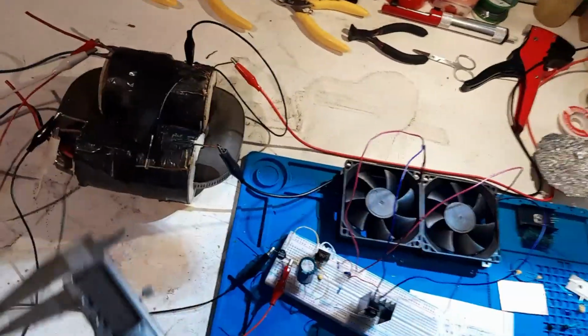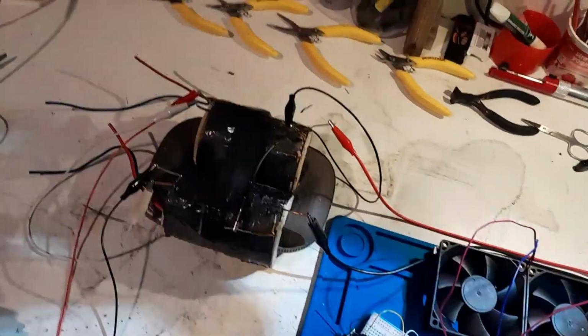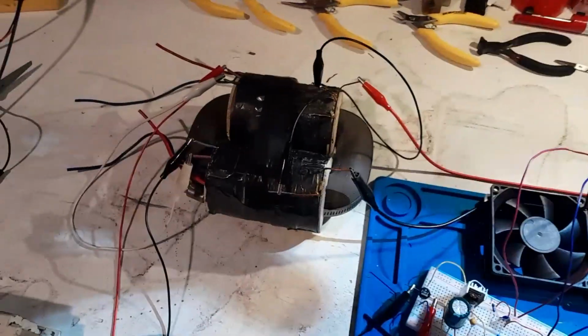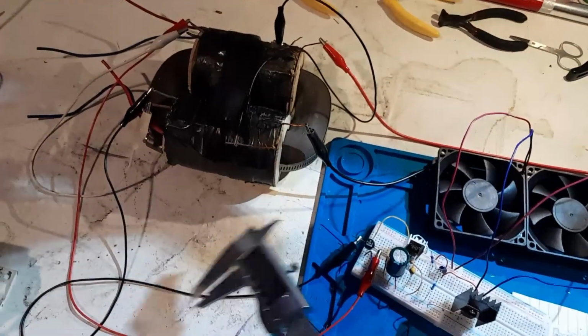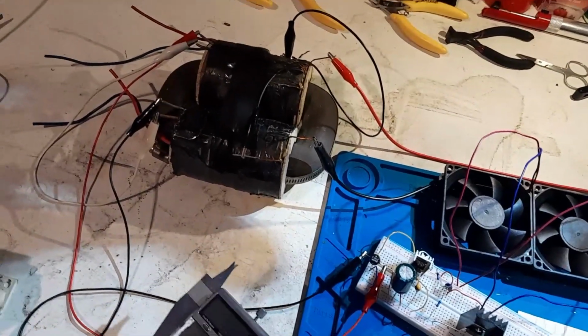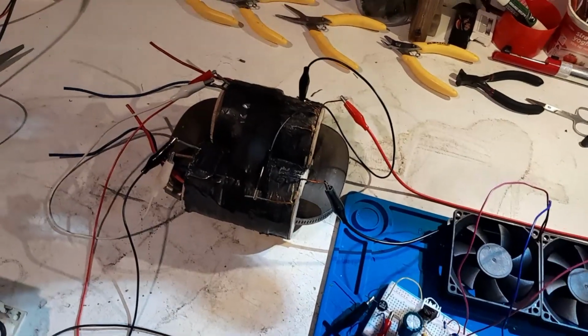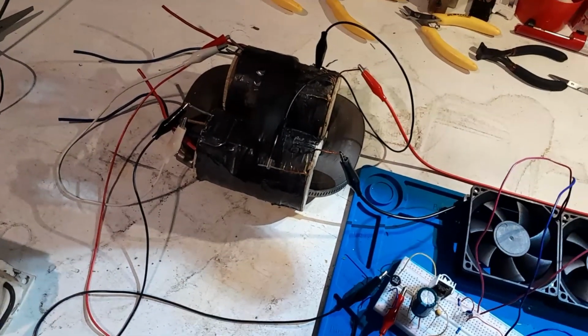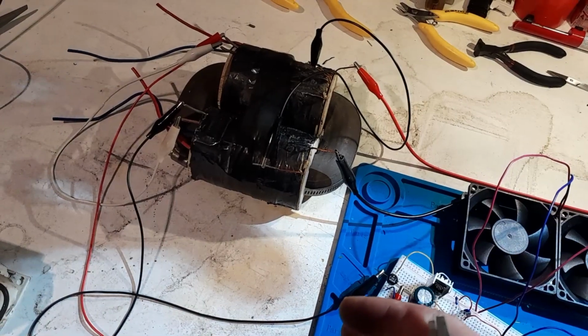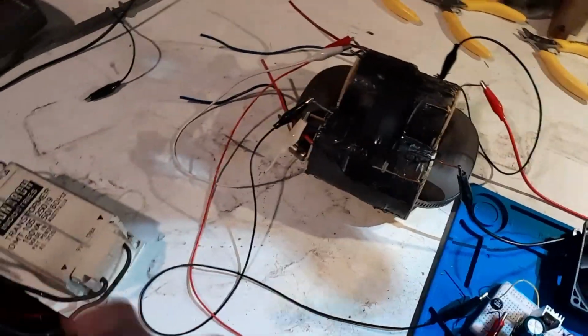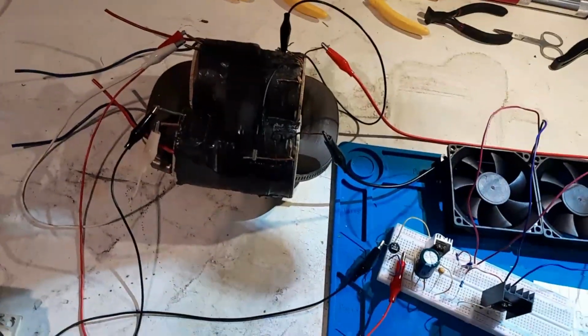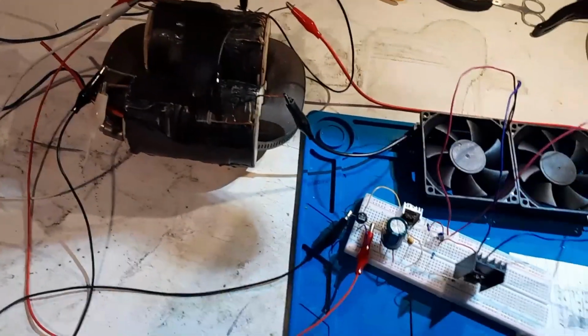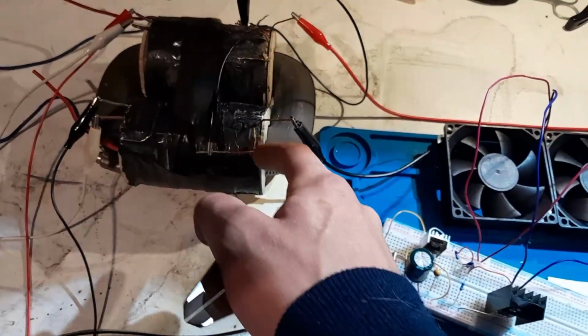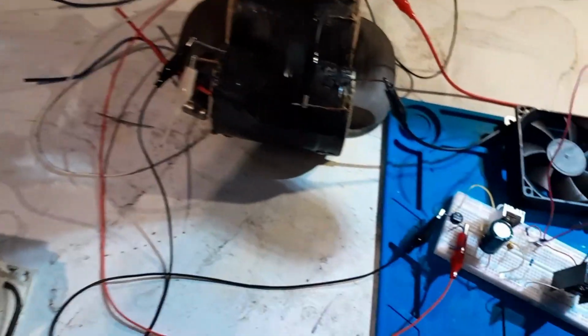There we go, this is a 750 VA transformer. Now the thing to consider when adding another transformer to boost the primary voltage is that it doesn't need to be the same VA. What you need to work out is the percentage of the voltage you're making up with the boosting transformer, and you need to be able to handle the VA for that percentage of voltage. Also, the winding must have the same current capacity or greater than the primary winding you're going to boost.